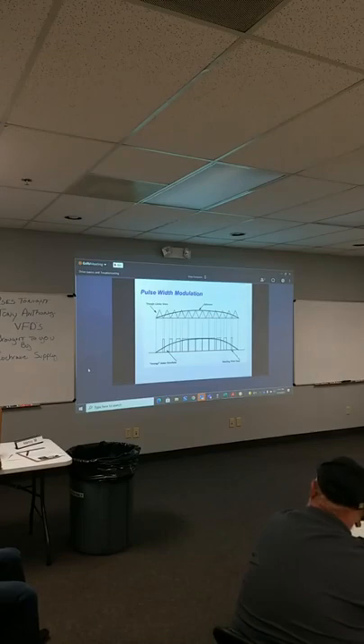So we're not sending an AC out, we're actually pulsing DC to make it look like AC power to that motor. And we control the width of the pulses, and then you see how it builds up the motor waveform. Little pulse, small build, wider pulse, small build a little bit more, and that is the power underneath that curve that the motor sees that simulates the waveform.